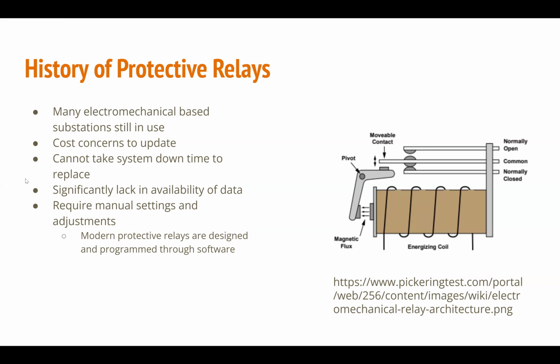There's also the aspect that you cannot take system downtime to replace it. In some cases we have electromechanical relays running a substation that's absolutely vital, and we might want to update parts of it - there are better ways to do it now, which I'll show you in a minute - but as of that point it's working well enough. They don't want to completely remove the substation and take like six months of downtime to replace it with a new one, and when I say six months that's the absolute minimum for teardown and build back up. Generally it's significantly longer, especially now with very long lead times for equipment. That's another reason you'll still see this stuff out there, even though it's bordering on 50 years old at this point.